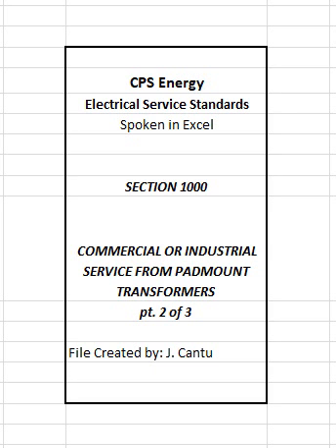2. For copper cable, lugs shall be pressure screw type and suitable for the conductors. For aluminum cable, lugs shall be compression type suitable for the conductors. Customer shall coordinate with CPS Energy prior to installation of compression lugs on their cables to ensure proper alignment of lugs with transformer secondary terminals and provide the necessary compression tools.